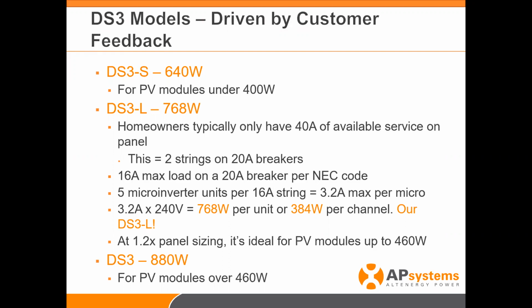So no one had ever really done this before, which is to work the math backward from the allowable amount of amps per circuit breaker to come out with the ideal wattage. And so this also maximizes the amount of energy that you are able to put through on each of those breakers. So it comes out to 384 watts per channel, which makes it ideal for PV modules up to 460, 480. So for the DS3S, PV modules under 400, for the DS3L, PV modules up to 460 or 480, and for the DS3 at 880 watts, for any PV modules that are over that amount.